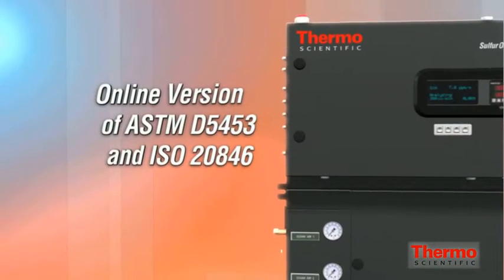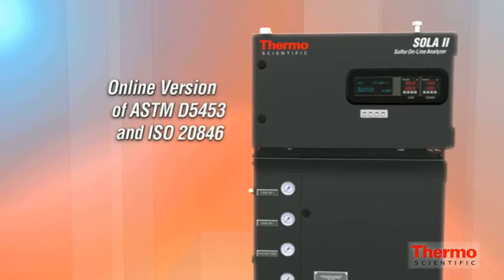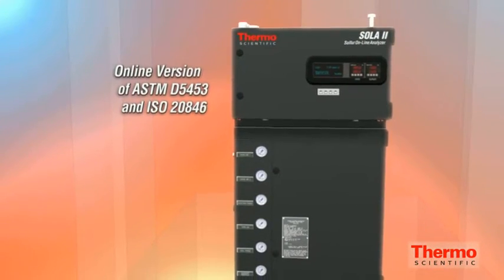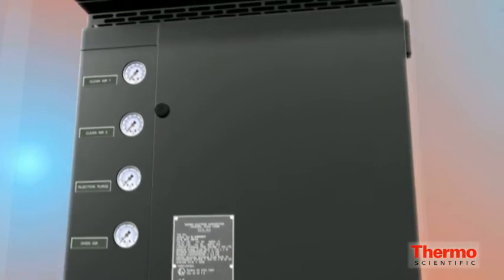The SOLA-2 is an online version of the well-accepted ASTM D5453 and ISO 20846. Each method describes the determination of total sulfur by sample combustion and pulsed ultraviolet fluorescent spectrometry.